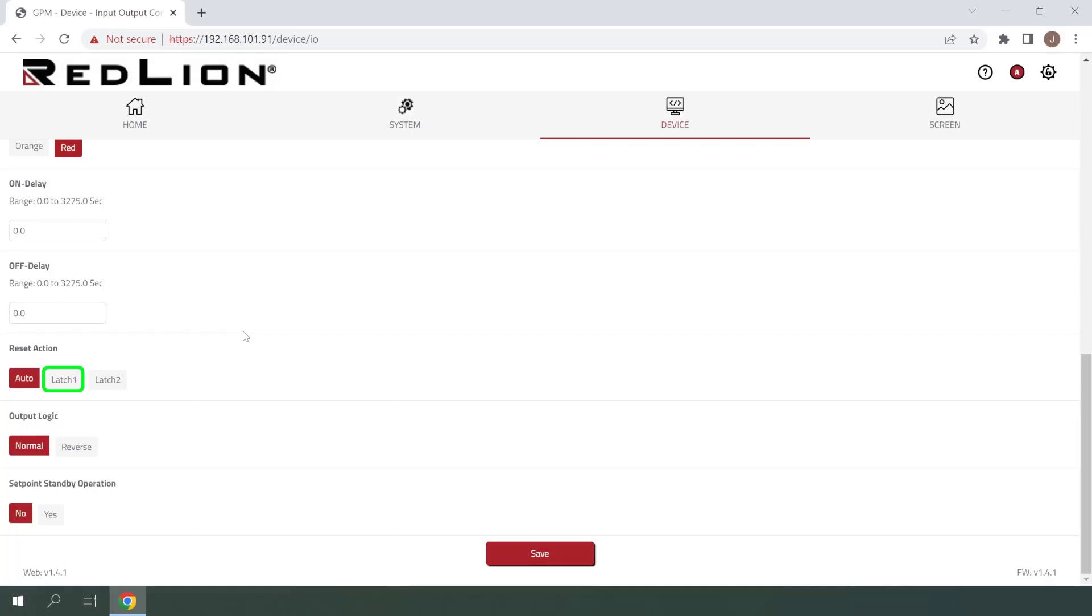Latch 1, or Latch with immediate reset alarms, will stay on until they are reset with a function key or user input, which can be done even if trigger conditions are still present. Latch 2, or Latch with delay reset alarms, will stay on until they are reset with a function key or user input, and trigger conditions are no longer present.